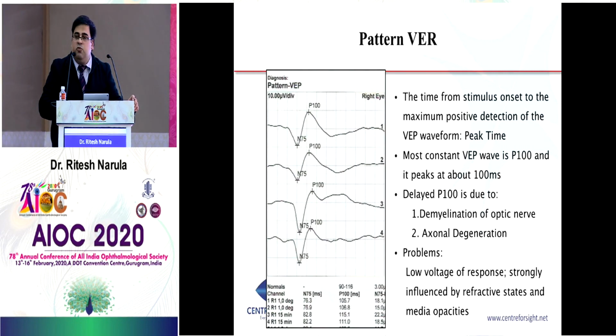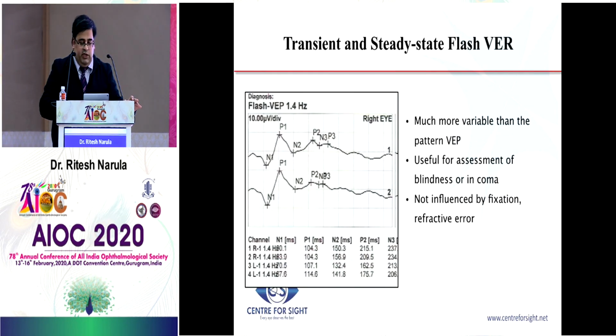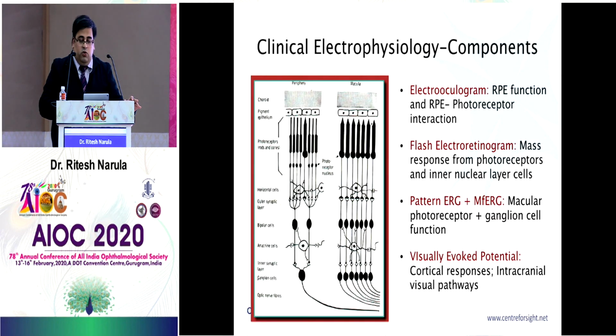Important to remember is that both pattern VEP and pattern ERG are very low voltage responses and very sensitive to fixation and visual acuity. So the patient should have a decent amount of fixation on the pattern. If the patient is not fixating, or is not refractively corrected, you will not get good responses in both pattern VEP and pattern ERG.